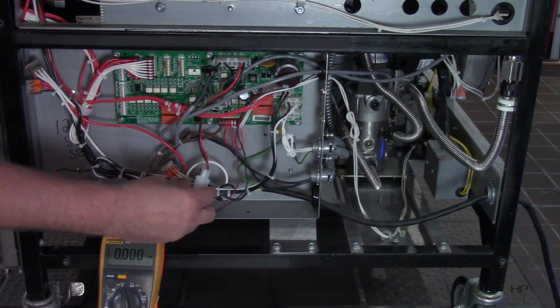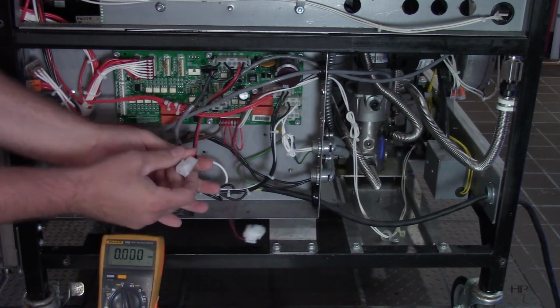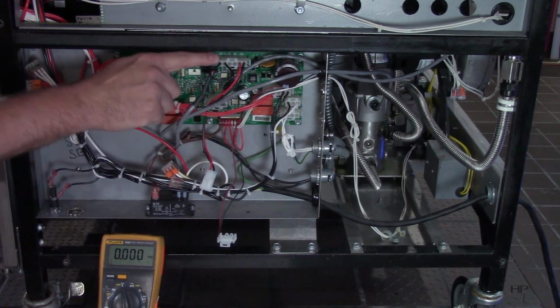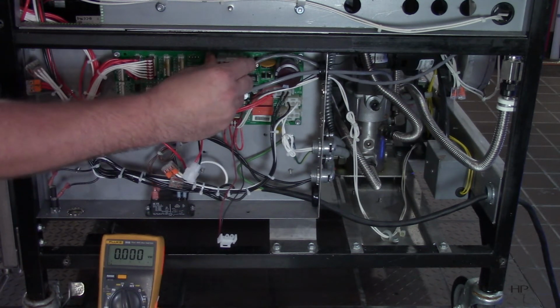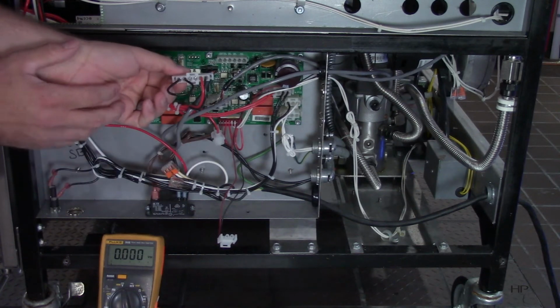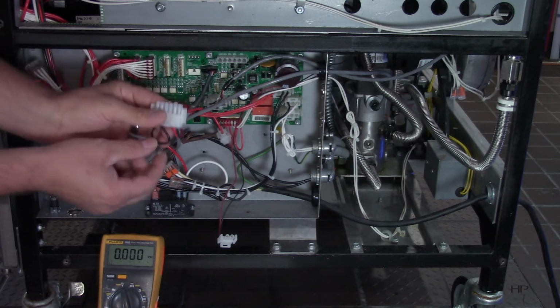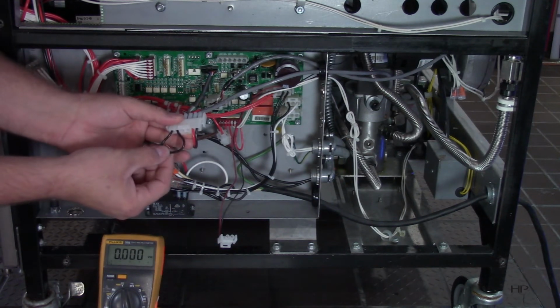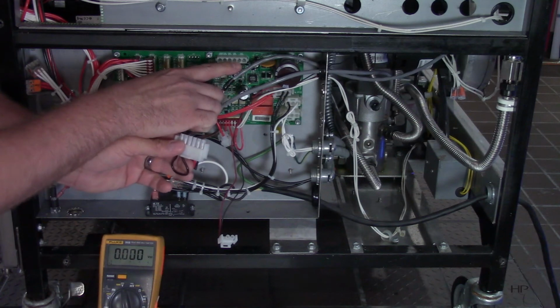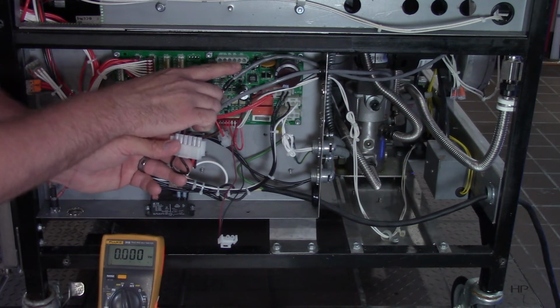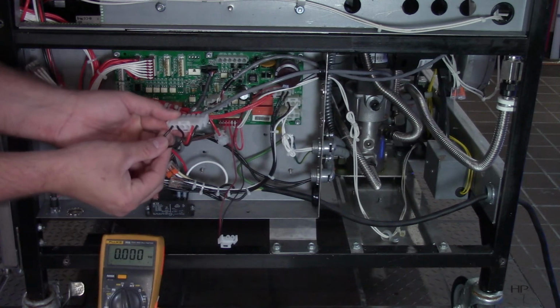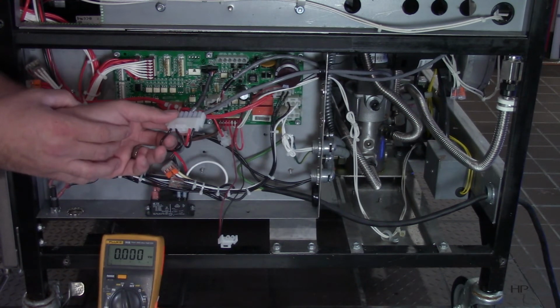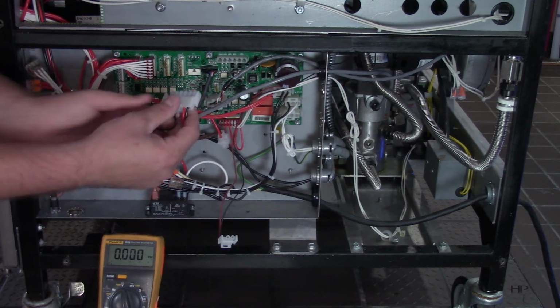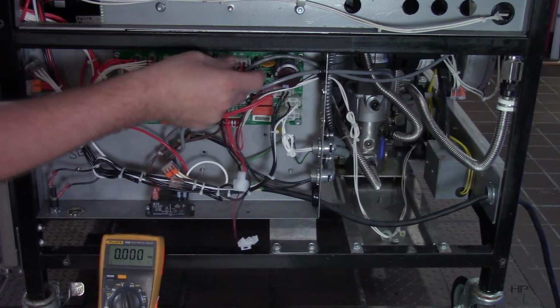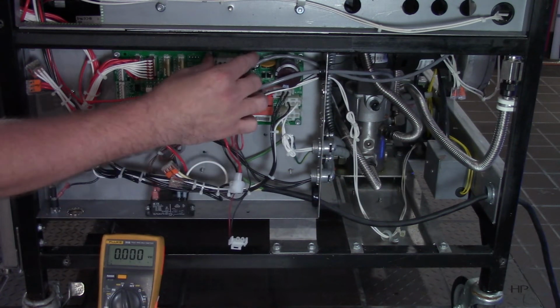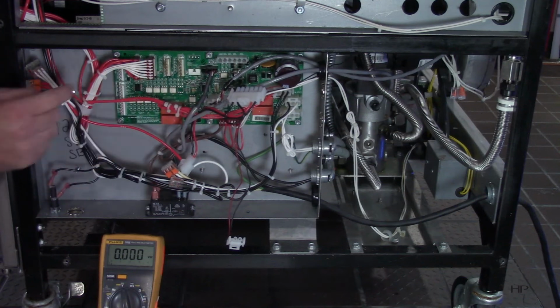Anytime we're checking for our DC voltage coming out of this connector right here, we want to make sure that this 6-pin plug is plugged in. The reason being is because you can see on this plug it has this jumper wire right here. If this AIF board does not see this jumper wire, you will never get your voltage coming out of these pins here, your 24 volts DC for your encoder motor. If it doesn't see this jumper wire, this AIF board thinks it's a solenoid valve setup. So it's critical that when we're doing our check that we have that plugged in and we check it here. Because if we were to have this unplugged and try and check our voltage here, we'll never get it.